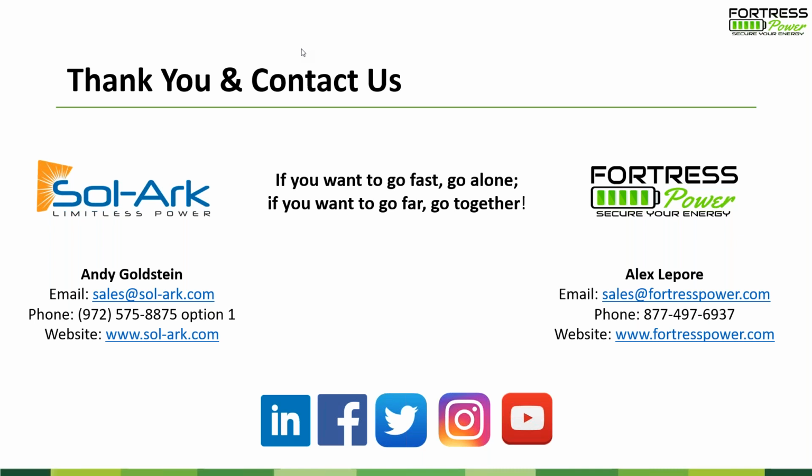Great. Just one quick comment. It's just a typical calculation when you do the assessment for the off-grid system. You need to look at the peak power and then the continuous power consumption from the customer to decide how many inverters and how many batteries you need for the whole system. You can contact us and we'll help you size it out. We have our sizing tool. Yes. We can help you size out the system you want. Agreed on that comment. Yes.